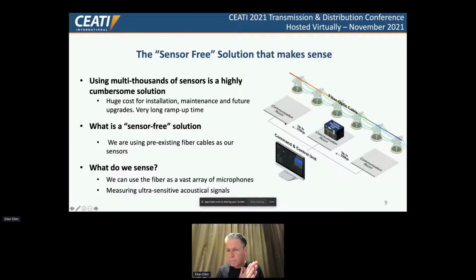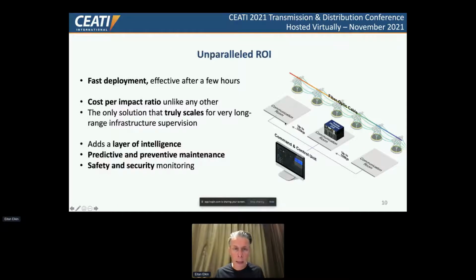Basically, just by placing a system in a pre-existing communication room in a substation and plugging it into the fiber, that's the whole installation needed. Once you do it, 100 kilometers of fiber is covered. If you have thousands of kilometers, the only installation needed is a system every 100 kilometers, or a dual system every 200 kilometers. That's it.